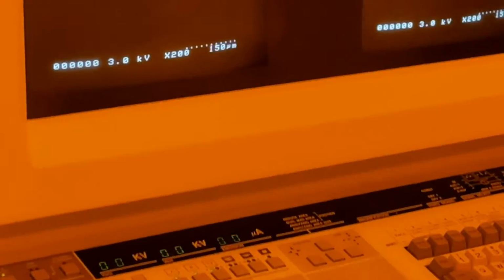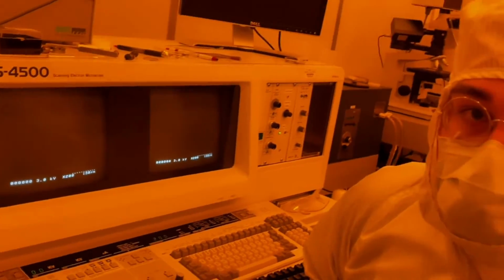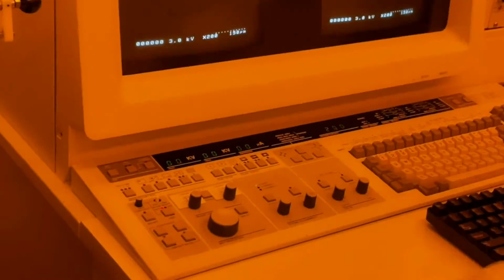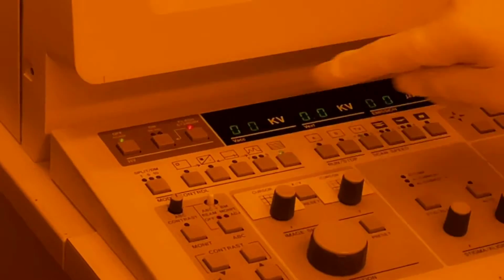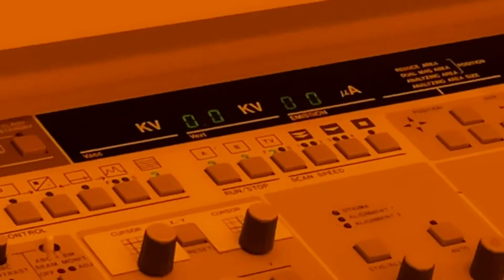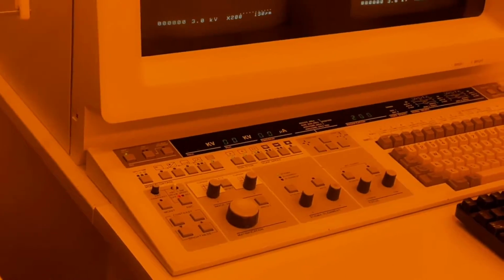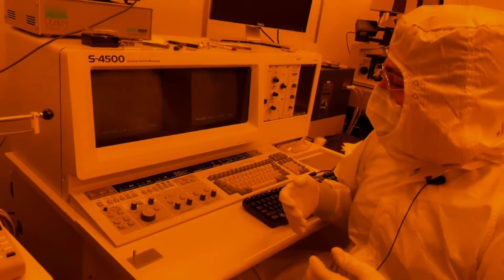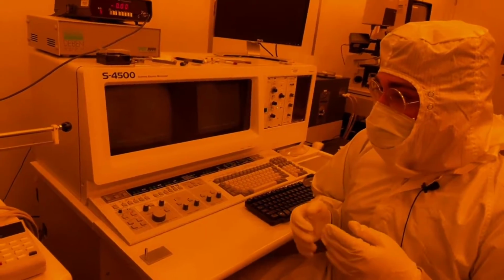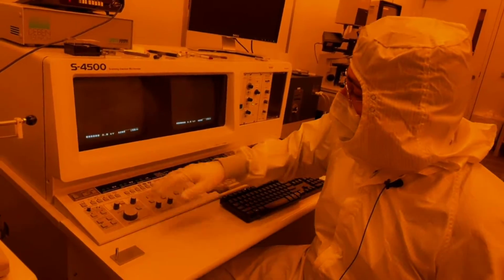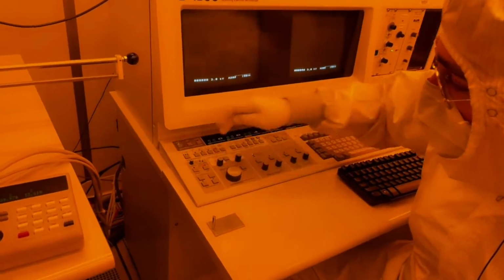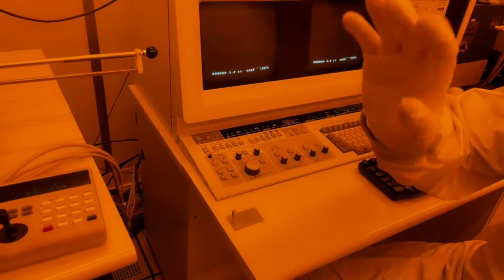If you're the first one to use the system in the day, you want to flash the tip. You do that by pressing the flash button. You'll see the LED here will start blinking. Press the on button, and you'll see that the emission current will spike. That's a current flash. And when it does that, that basically runs a current without a high voltage through the emitter tip, and that is supposed to eject any contaminants on the tip. So now we can turn it on. Now that we flashed it, you press the on button. You can hear the aperture open.